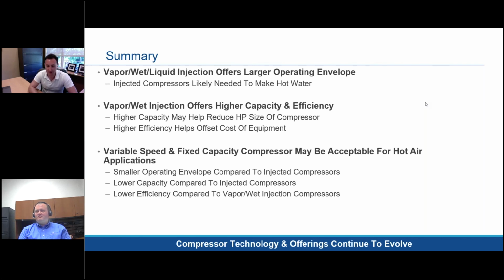Okay, great. Next I have, with those refrigerants, with the 410A phase outs, do you guys have any performance on these comparatively? We do. We share that with the OEM. The compressor performance may not be reflective of what the OEM is actually seeing though, because 454B and R32 are going to have different heat transfer properties from each other and from what R410A has. So typically we're seeing increased efficiency in 454B and R32 with the compressor itself, but the main efficiency difference is really going to be system related. So I'll give you an example.